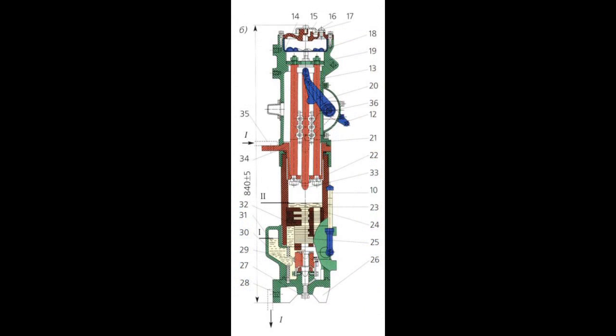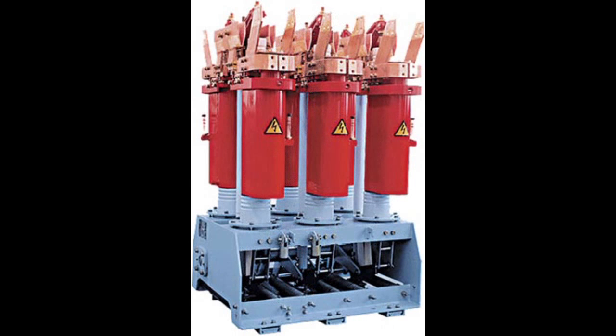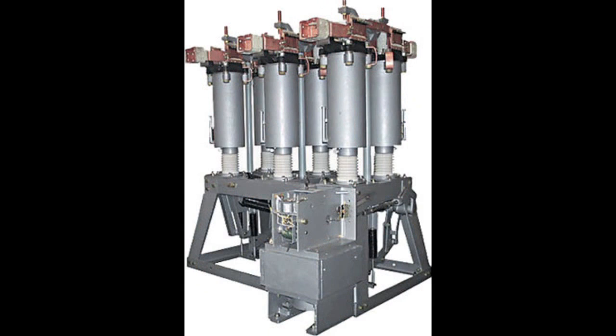This increases the dielectric strength of the break. Two pairs of operating and arc suppressing contacts are used with high rated currents. Operating contacts are situated on the outer side of the circuit breaker, while the arc suppressing contacts are inside. By changing the length of the arc suppressing contacts, you can first break the operating contacts without the formation of an arc.